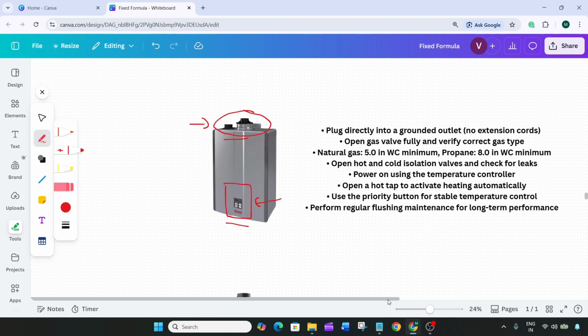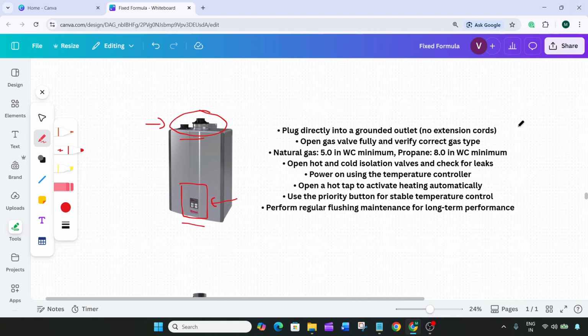Never use extension cords or adapters, as they can cause unstable power and safety risks. Second is the gas valve setup. Make sure the manual gas valve is fully open and confirm the gas type matches the dip switch settings on the control board. Natural gas requires a minimum of 5 inches water column pressure, while propane requires at least 8 inches. Third is water flow setup.